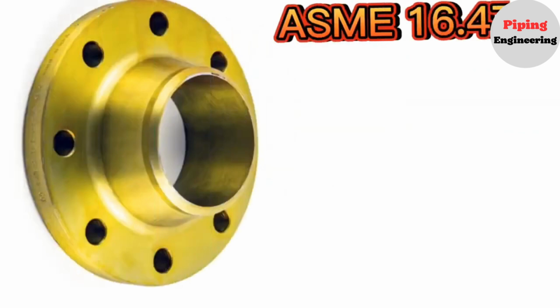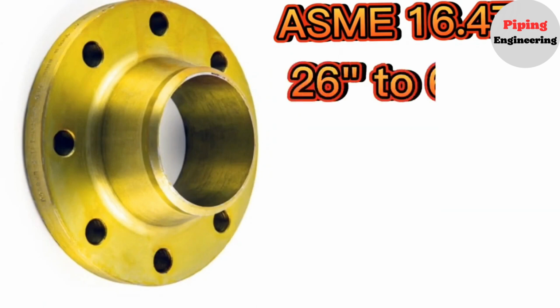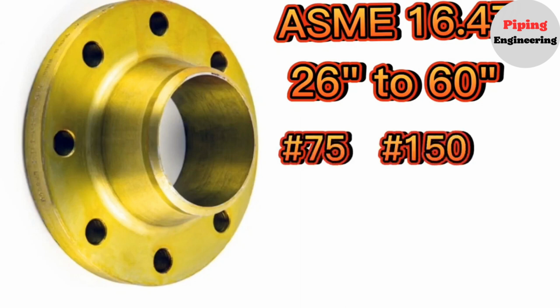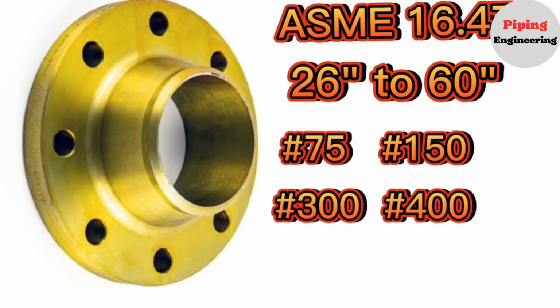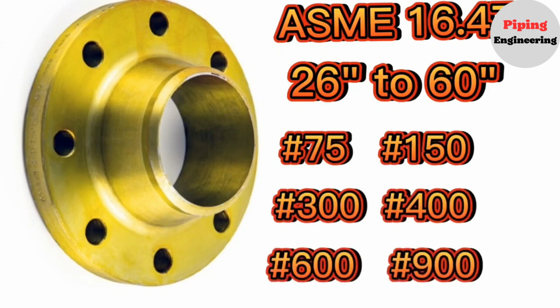ASME B16.47, large diameter steel flanges. This standard provides dimensions only for weld neck flanges and blind flanges for size range 26 to 60. Rating class designations provided are 75, 150, 300, 400, 600 and 900.